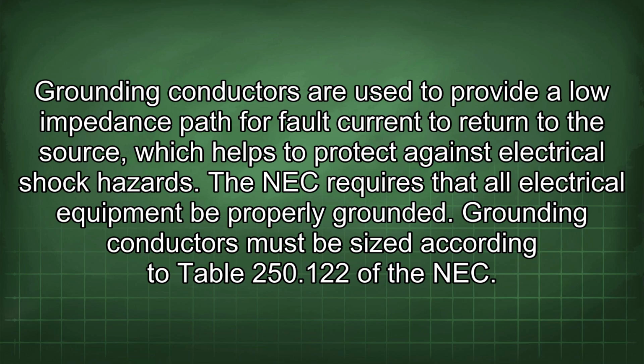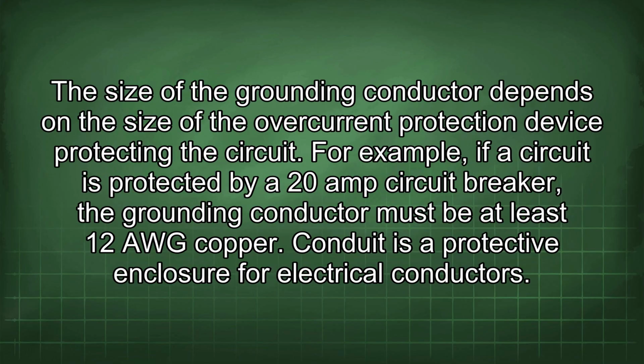Grounding conductors are used to provide a low impedance path for fault current to return to the source, which helps to protect against electrical shock hazards. The NEC requires that all electrical equipment be properly grounded. Grounding conductors must be sized according to Table 250.122 of the NEC. The size of the grounding conductor depends on the size of the overcurrent protection device protecting the circuit. For example, if a circuit is protected by a 20 amp circuit breaker, the grounding conductor must be at least 12 AWG copper.